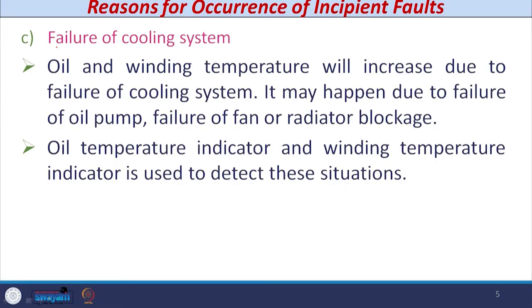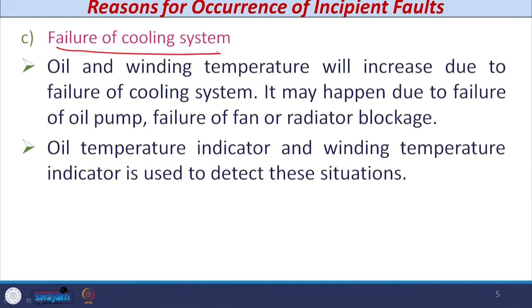We need to carry out regular cleaning of the silica gel and change it if required. The third reason for incipient faults is failure of the cooling system. Power transformers are very large, and oil is normally used for cooling. Due to failure of the cooling system — caused by failure of an oil pump, failure of a fan, or blockage in the radiator — the oil and winding temperature will increase. To detect this abnormality, an oil temperature indicator and winding temperature indicator are used inside the transformer.